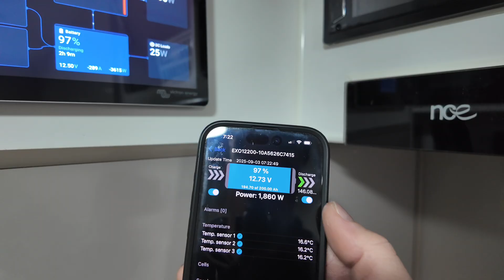That's because we're running active to one battery, neutral to the other battery, with links in between. Ideally you want those cables to the inverter, the active and neutral, to be the exact same length, which we try to do all the time, to marry them up as best as possible. But it also depends on the shunt placement and whatnot.